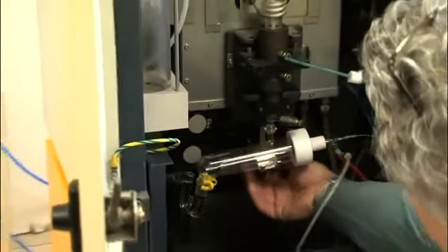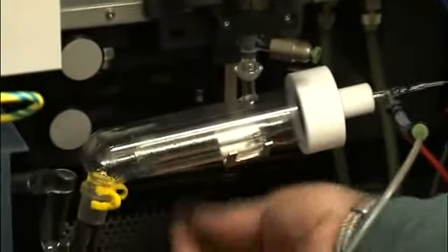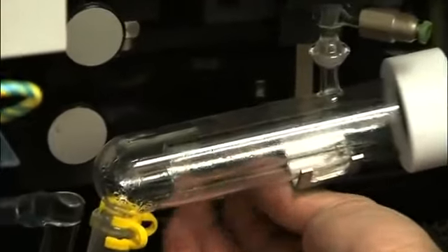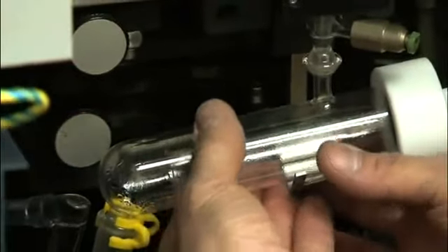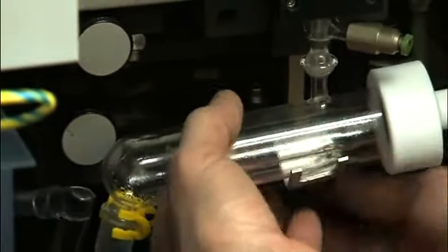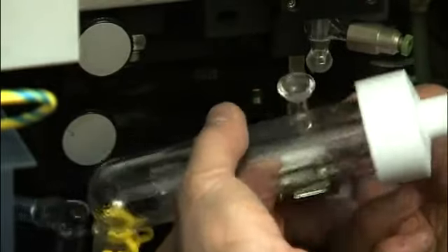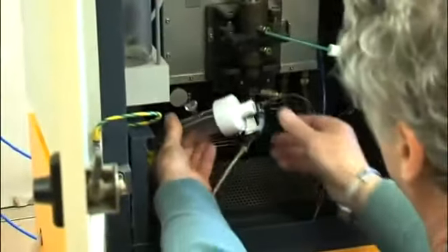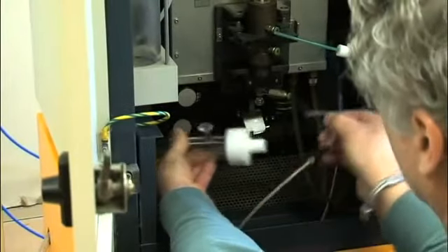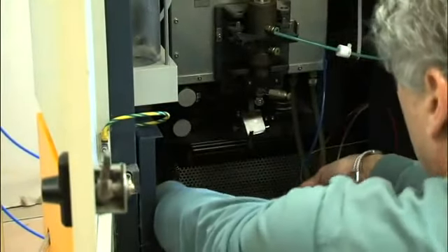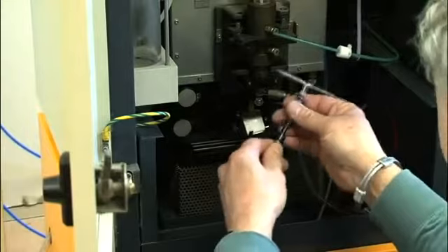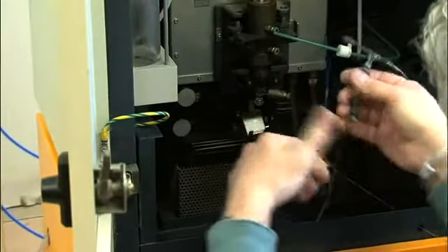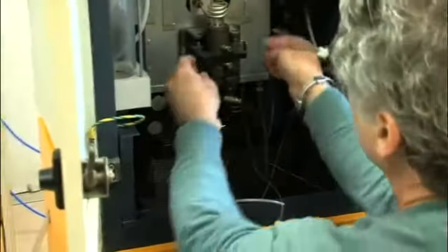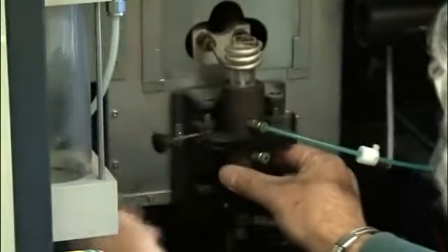and then there's a lock nut on the device that holds the spray chamber. It's over on the left side. If you loosen it, then that allows this clamp to come down, and then your spray chamber comes out like this. Your torch, you loosen this knob so you can swing that over and your torch comes out like that.